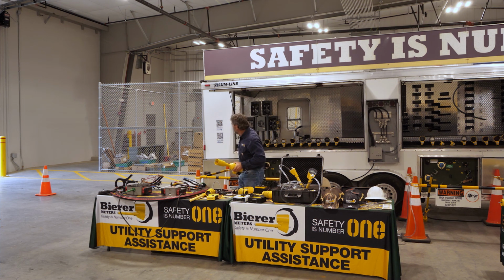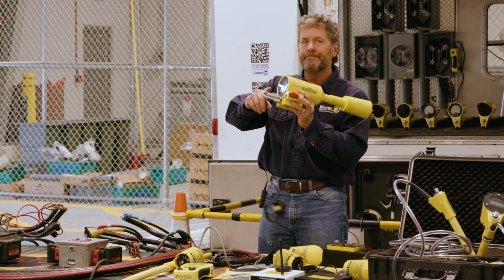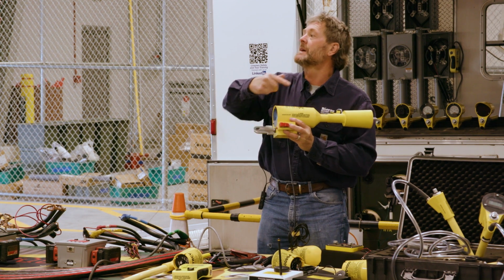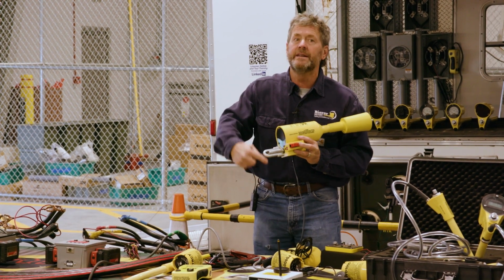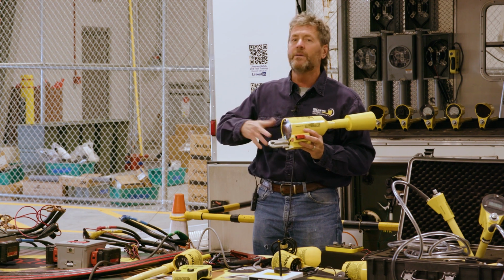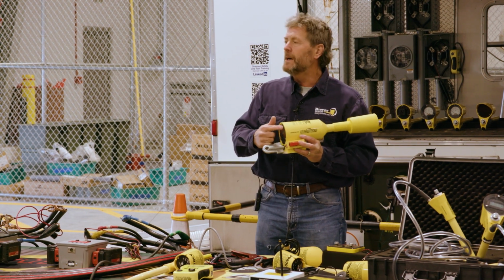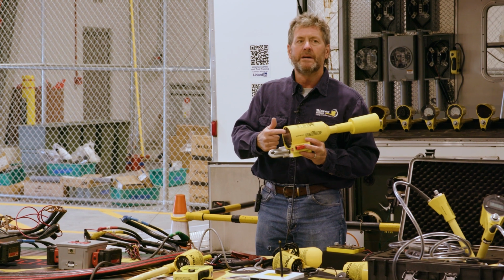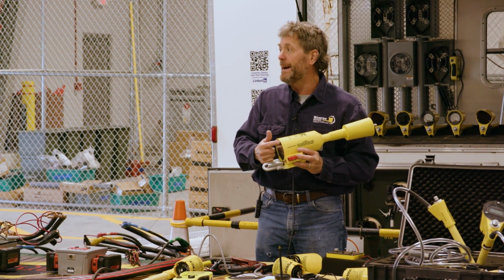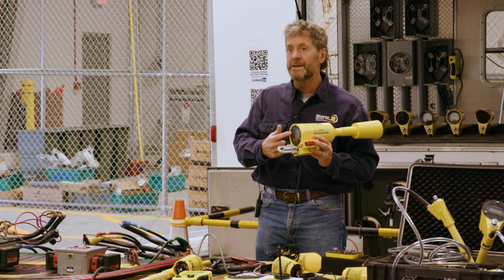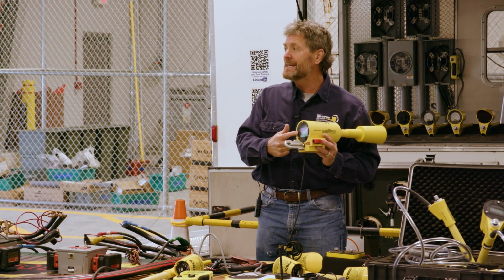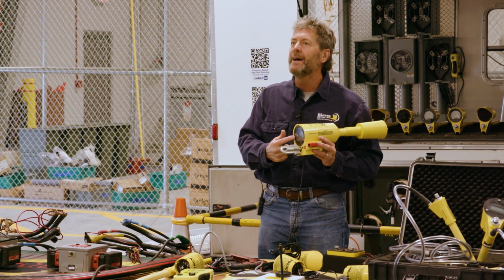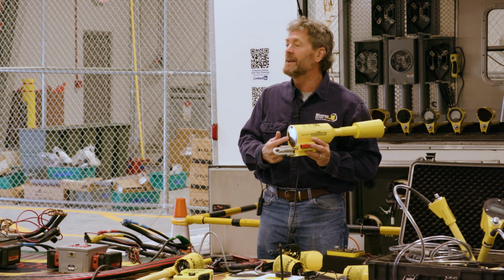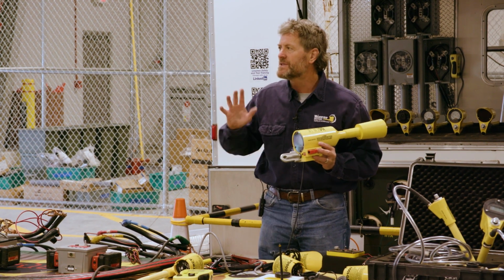You got a feed through, you got your primary isolated, de-energized, and you just plug it in that feed through, turn it on. You got it on your hot stick, turn it on, and the needle goes up, charges that cable. If the cable's good, the needle comes down within a few seconds and stays down, the cable's good. If the needle goes up, stays up, or it bounces, then the cable's bad. If the needle goes up and stays at maybe 20% and hangs at 20%, it's just telling you you have some bleed on the cable, it's an old cable, and it's a long run. But it's fine. The cable's still fine.